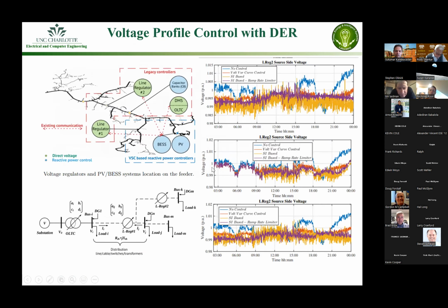Then we move to profile management, where we find the regulator outputs based on measurement, create a sensitivity matrix for the entire system, and see whether we can manage the profile properly. Here's an example of the secondary side voltage regulator output with volt-VAR control versus sensitivity-based volt-VAR control, showing the profiles are much flatter with sensitivity-based management.